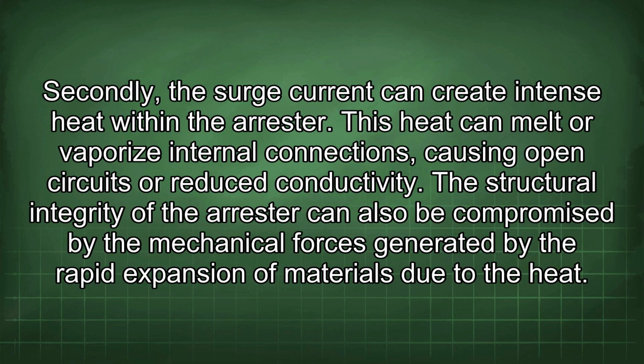Secondly, the surge current can create intense heat within the arrestor. This heat can melt or vaporize internal connections, causing open circuits or reduced conductivity. The structural integrity of the arrestor can also be compromised by the mechanical forces generated by the rapid expansion of materials due to the heat.